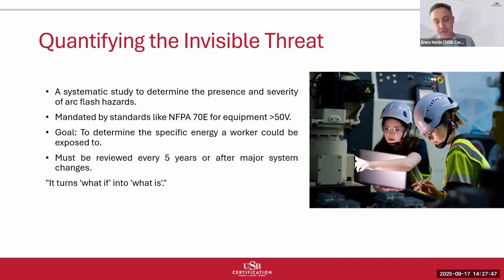Why? Because electrical systems evolve. New loads get connected, protective device settings get adjusted, equipment gets replaced with different characteristics. A location that was relatively low hazard when your building was new might be hazardous today. The analysis process involves several sophisticated calculations. Available fault current at each location when the short circuit occurs. Arc current based on system characteristics. Protective device clearing time. The most important thing is the clearing time. If the arc flash occurs, the current is still on the system. That's why we calculate the clearing time. Incident energy based on arc duration and distance.